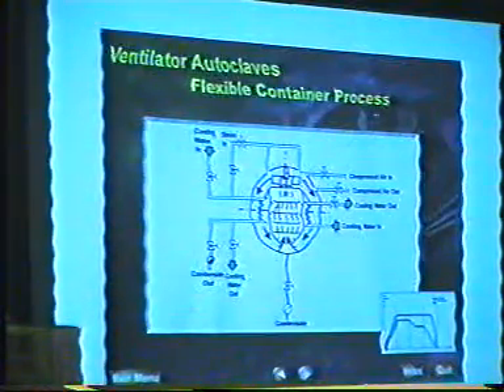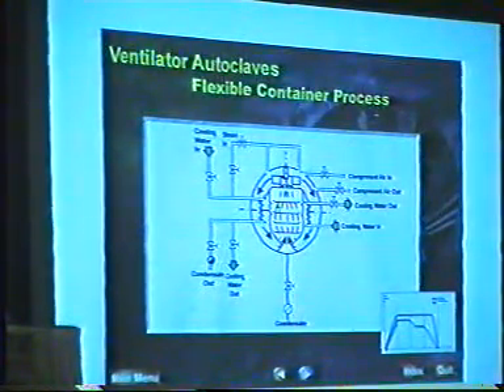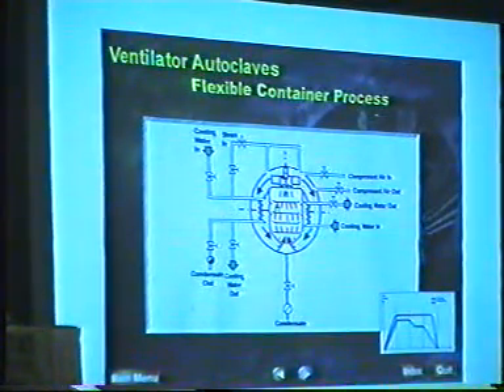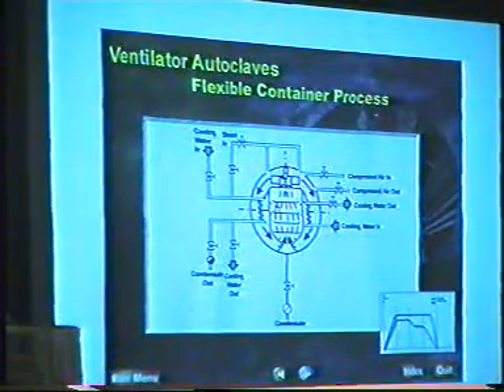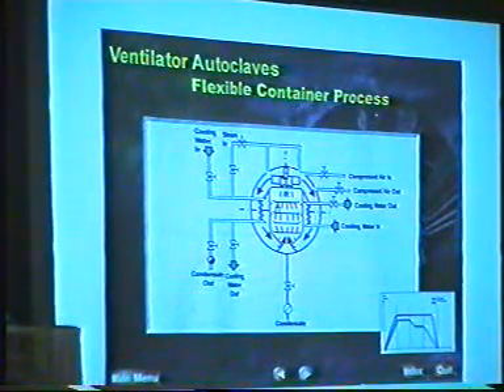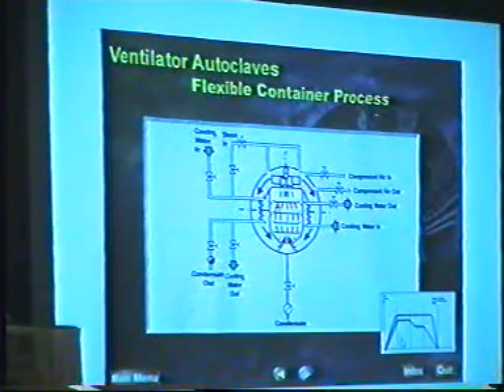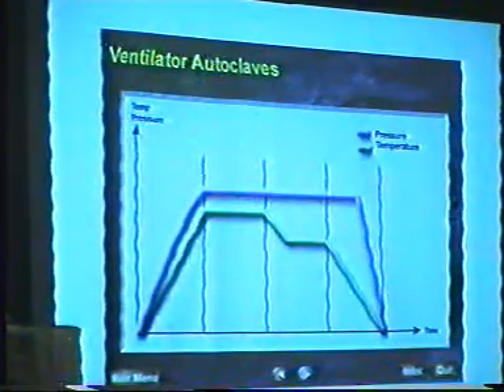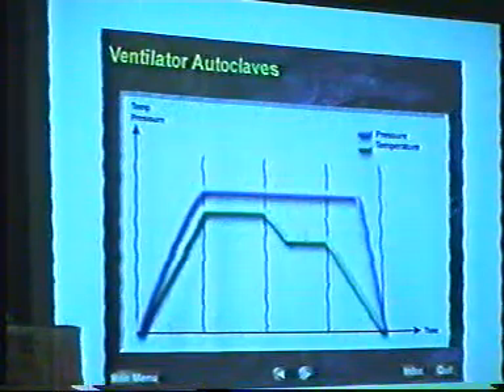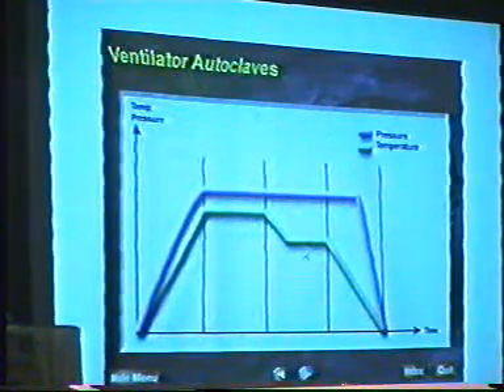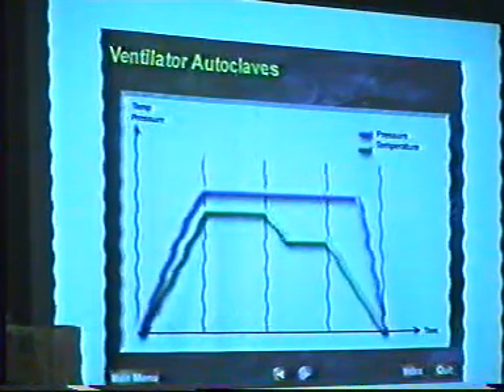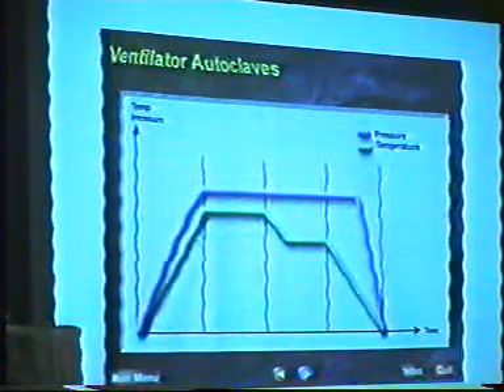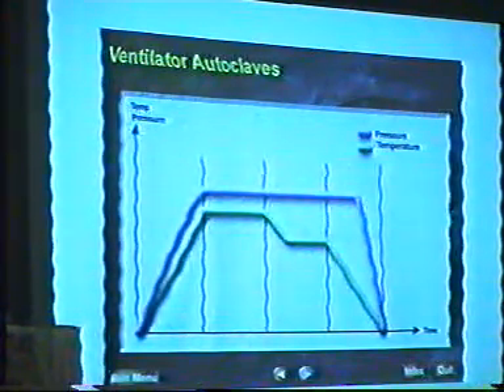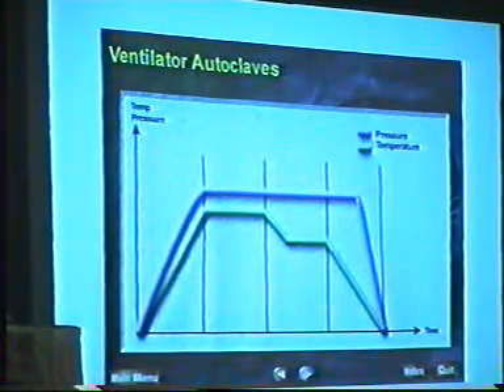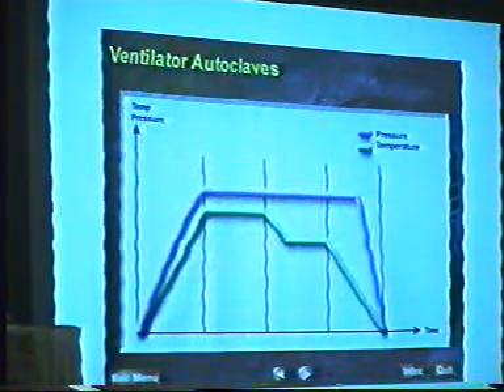However, ventilator has one feature which no other terminal sterilization system has, which is very, very important where pouches are processed. Depending on the composition of either PVC or laminates, there is a tendency of fogging, and defogging of these pouches is a big headache. In ventilator autoclave, the sterilization hold phase can be immediately followed by a drying phase, where the heating medium, which is a mixture of air and steam, is allowed to go out, and you dry with the help of hot air at a specific temperature for a specific time, and your fogging probably will be taken care of. It will go by itself.